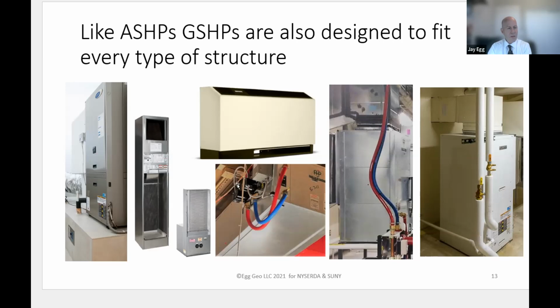And interesting to note, you can see the geothermal pipes tying into the heat pump, tied to the little fluid circulators that pump the fluid, the water, into the heat pump to provide the heat source and heat sink. Here you see a bigger commercial heat pump that provides the heating and cooling for maybe an auditorium or a cafeteria or a restaurant. And here's a more singular common area heat pump. The common thing you see with each of these is they have fluid pipes that are filled with water-based fluid that provide the heating source and sink for these heat pumps.